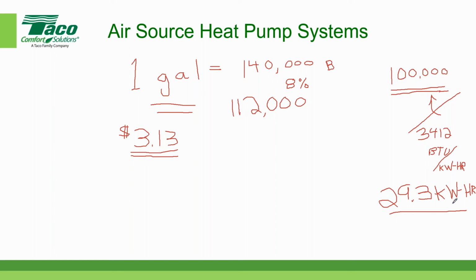Well, we said that electricity costs 20 cents per kilowatt hour, so I multiply that by 0.2, and magically I come up with $5.86. So what did I just figure out? If I generated 100,000 BTUs by burning home heating oil at 80% efficiency, it would cost me $3.13. If I did it with electricity, it would be $5.86. And that's with resistance electric heat. Remember, that's with a COP of 1.